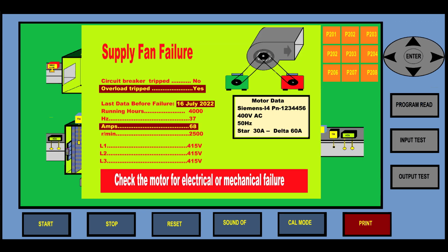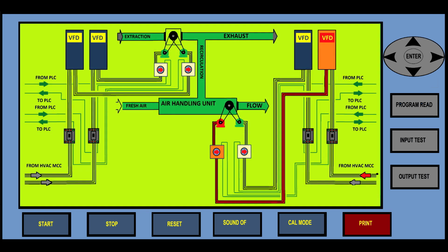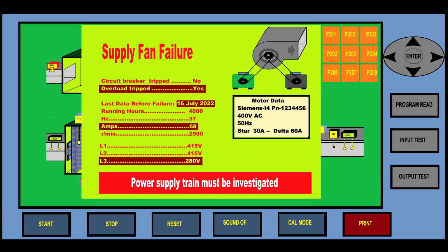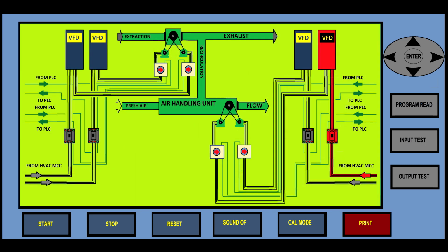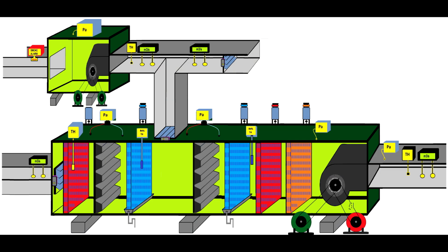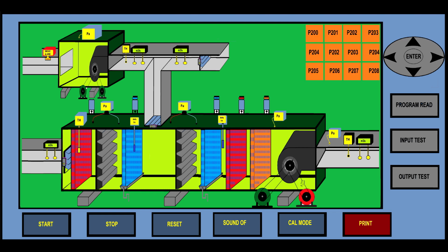The HMI will tell you, check the motor for electrical or mechanical failure. So when you go to the next page, the HMI will show you what to investigate. Or if you have, like in this case, a supply power failure, the HMI will ask you to investigate the supply. So actually it will direct you where you're supposed to go. This is the beauty of it.